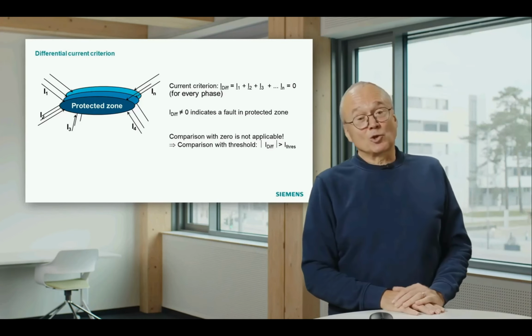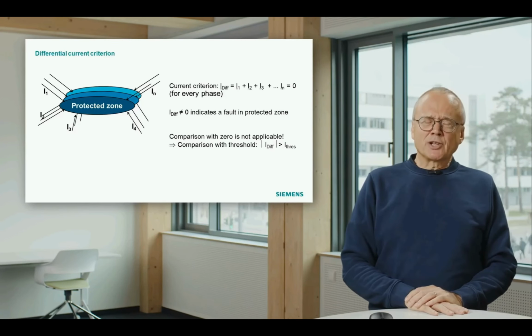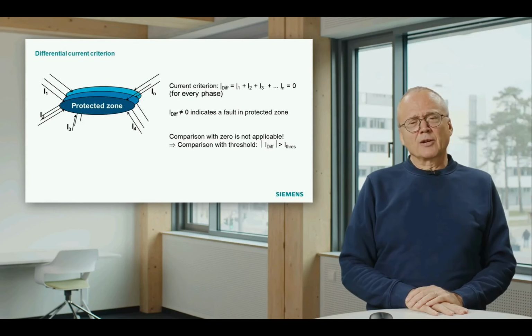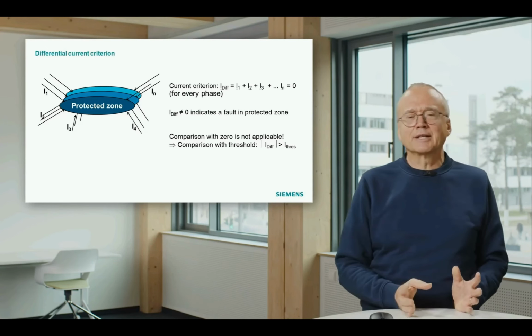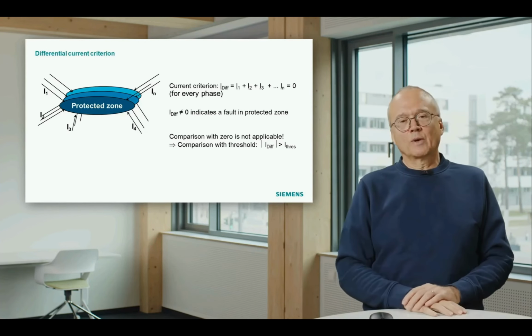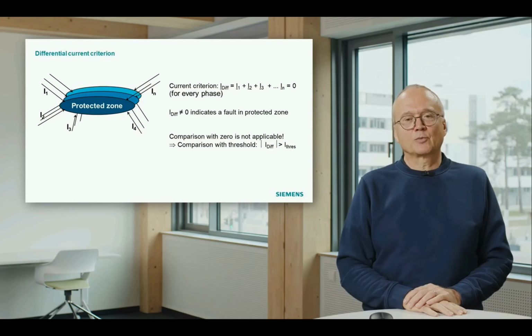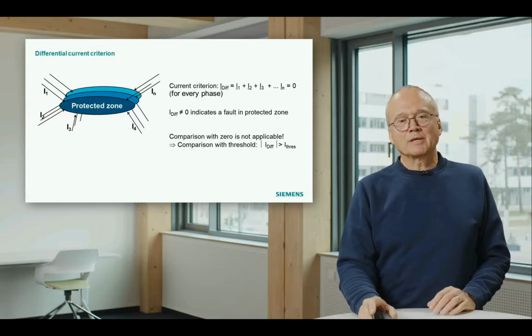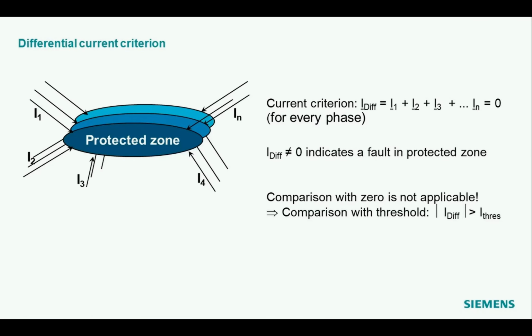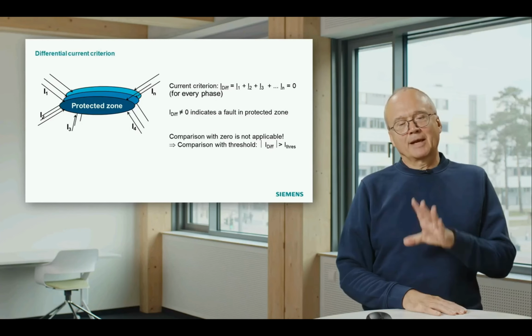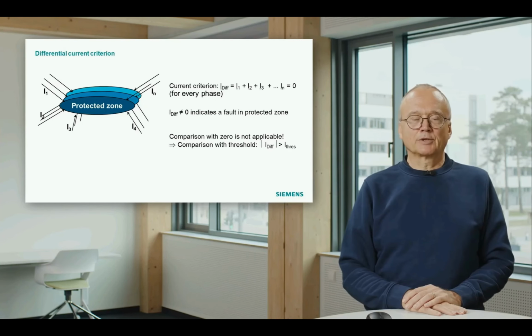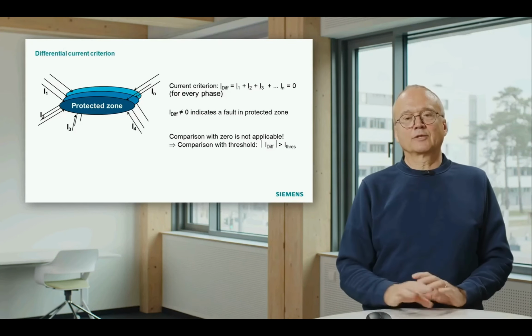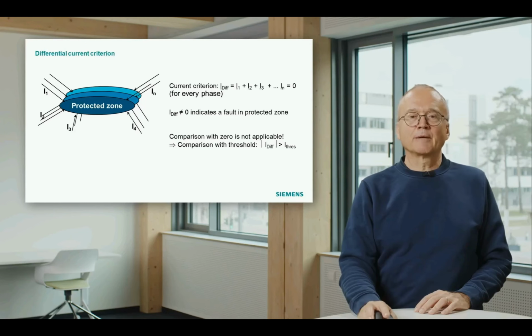You may realize in this context, just comparing a measured current with 0 and saying, okay, as soon as it is unequal to 0, there is a fault, is not a good idea. Of course, in real life, we must always compare it with a certain tolerance, with a certain threshold value. That means finally the differential criterion is we calculate the differential current and compare it with a certain threshold. And that is a little bit the tricky thing in differential protection, to define the correct threshold values. But the principle is a very simple thing.